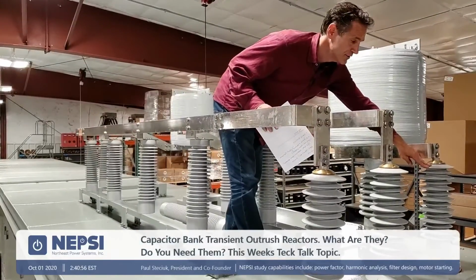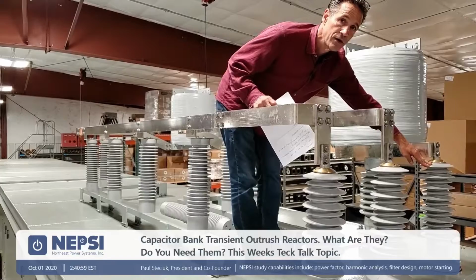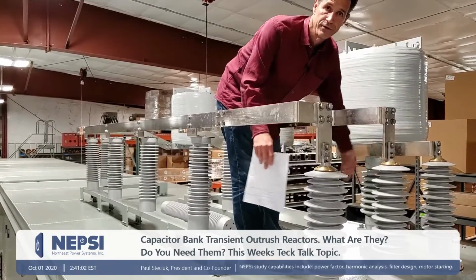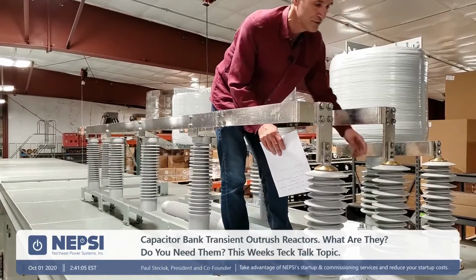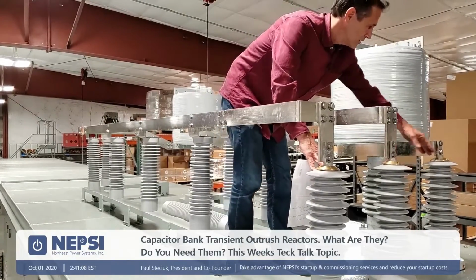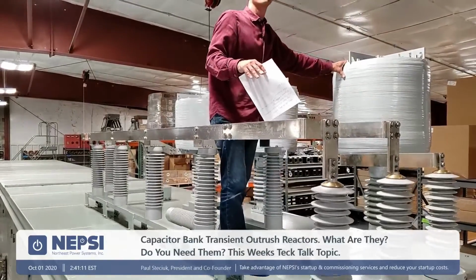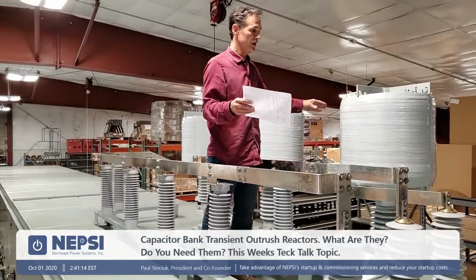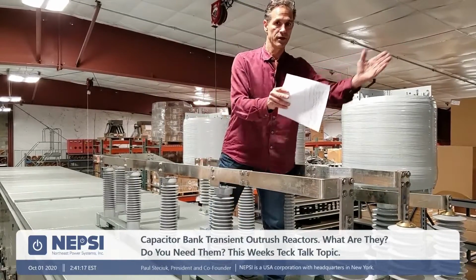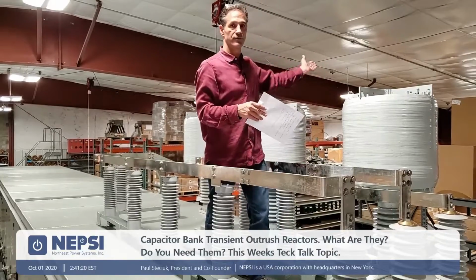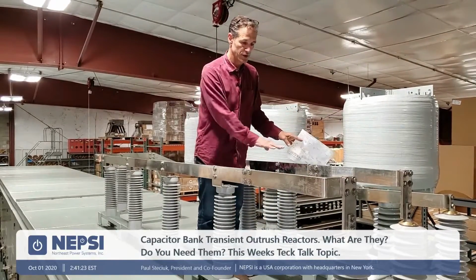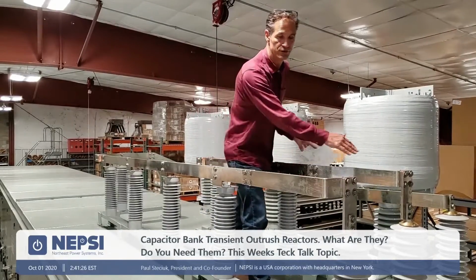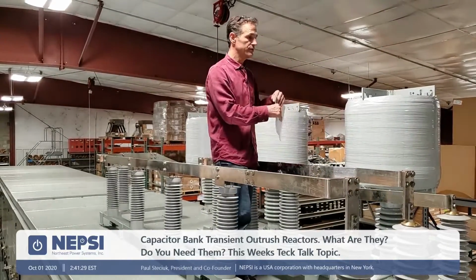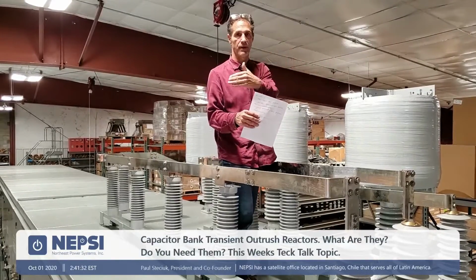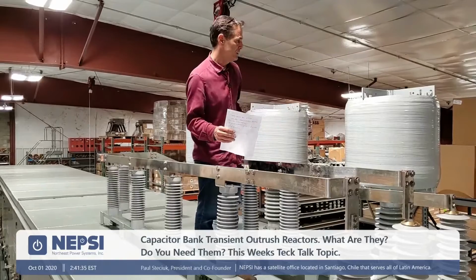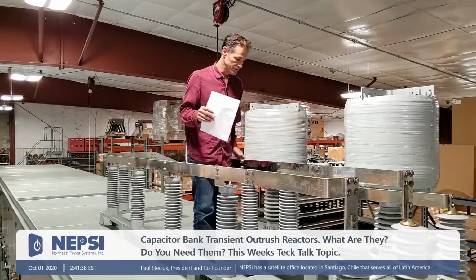All right, so we have bushings here. These bushings provide the power flow through the roof of this enclosure and then finally into our metal-enclosed system. So these are 250 kV BIL bushings, and we've got the main bus work here. So with air core reactors, we can orient the reactors so that you have entry from this side, entry from the front, or entry from the back. And what we do is we situate and move the bus work around here as well as the bushings to allow for entry into the enclosure through either the sides, the back, or the front. And that's really the essence of this air core reactor arrangement on the roof.